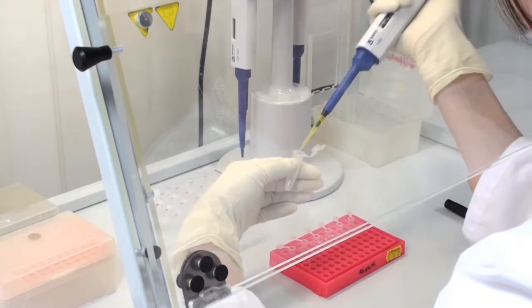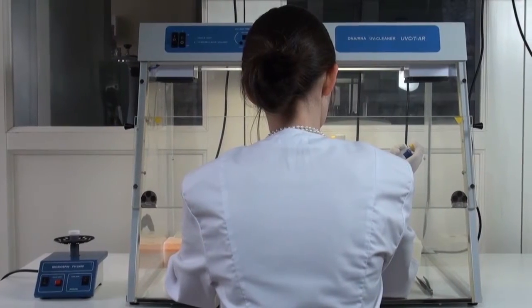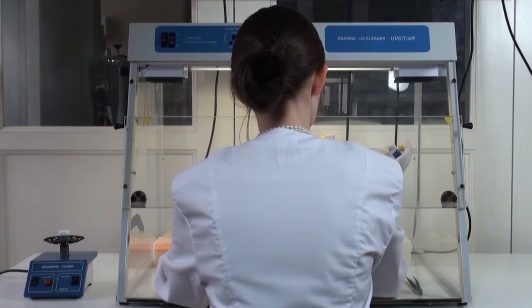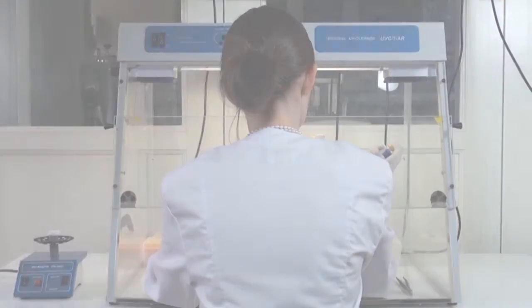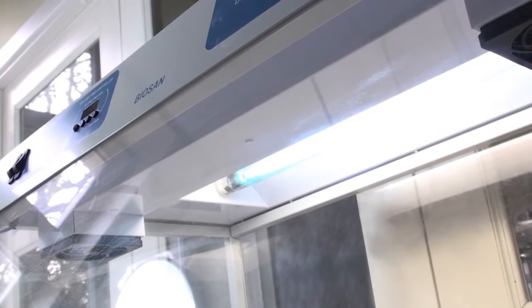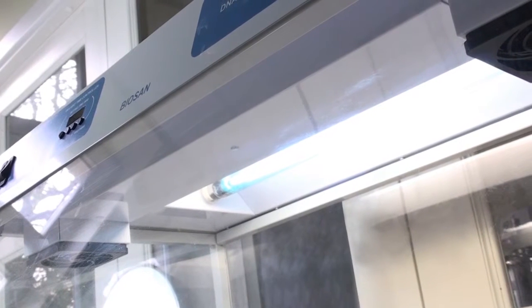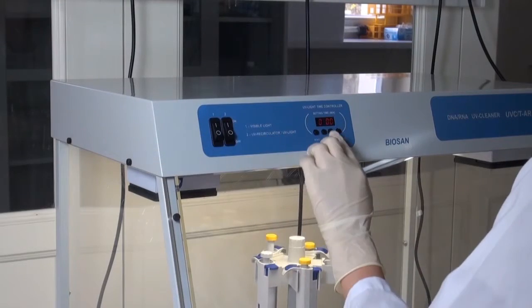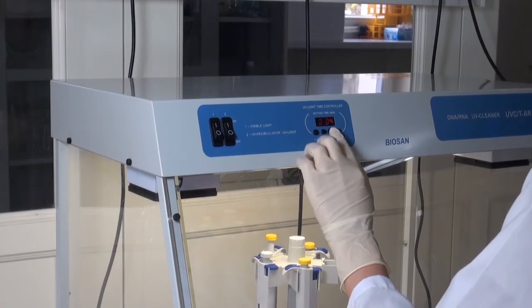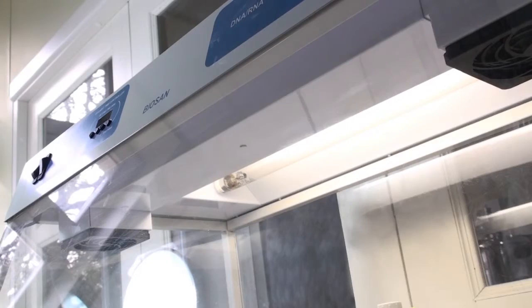All models are benchtop type, made of metal framework, glass or plexiglass walls, and working surface painted with powder enamel or made of stainless steel. UV cabinets are equipped with an open UV lamp installed in the upper hood. UV radiation from the open lamp disinfects the working area by inactivating DNA-RNA fragments during 15 to 30 minutes of exposure. A digital timer controls duration of the direct UV irradiation. A daylight lamp provides the proper illumination of the working surface.